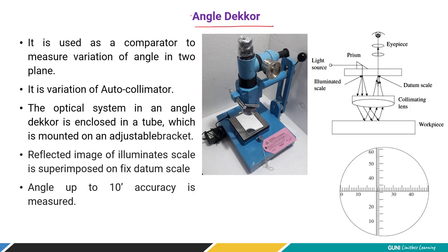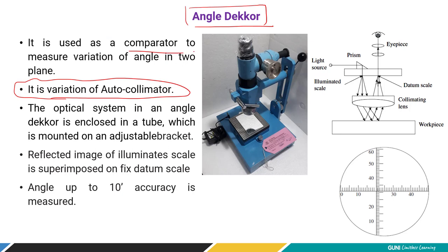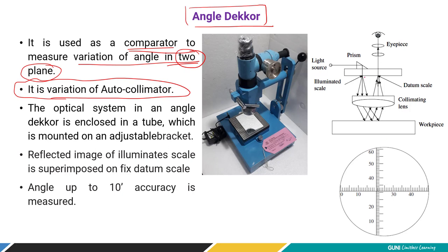The angle dekkor is another angular measuring device and is simply a variation of the autocollimator. Its first function is that it is used as a comparator to measure the variation of angle in two planes — this is important. By construction, the function is the same as the autocollimator, but there is a small change: it has two scales — one is a datum scale and the second is an illuminated scale.